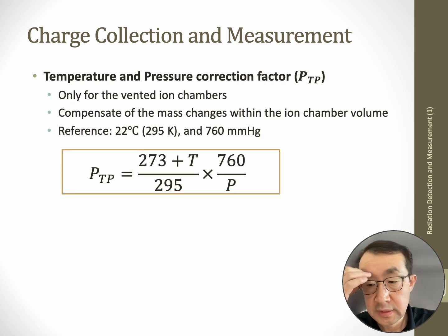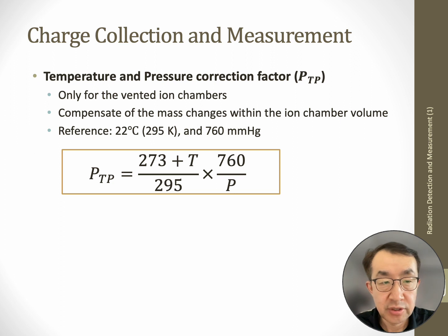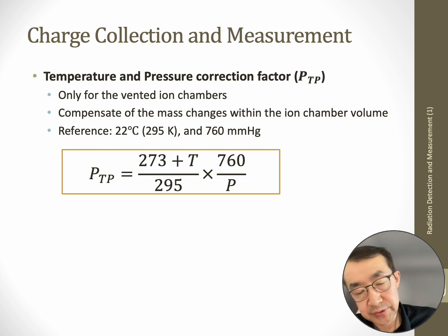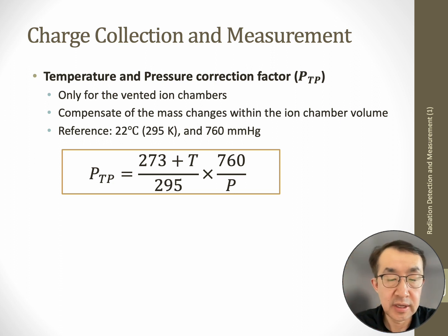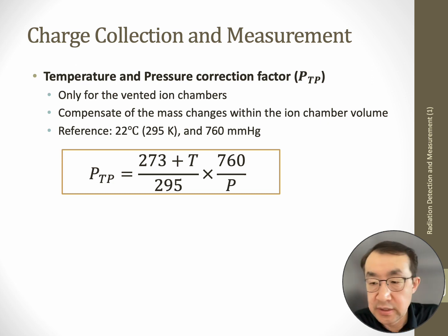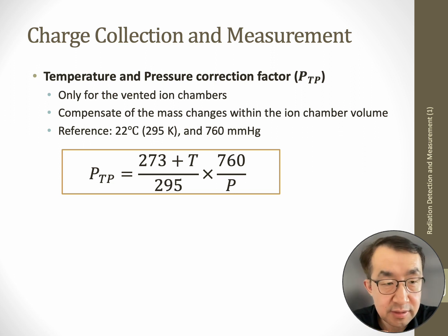So for these air-filled, gas-filled ion chambers, unless it is pressurized and sealed, you always have to talk about the pressure and temperature correction. It is only valid for the vented ionization chamber that I mentioned earlier. The temperature and pressure inside that active volume change as your environmental temperature and pressure change.